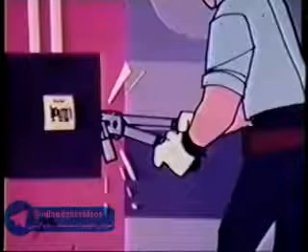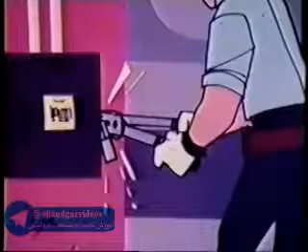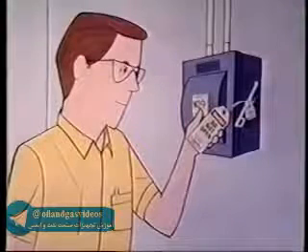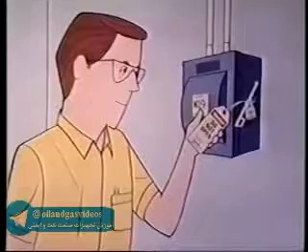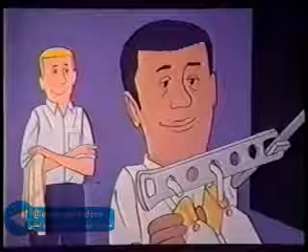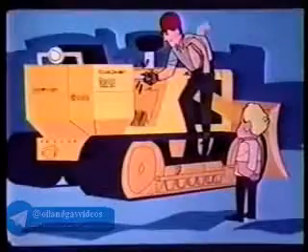The plant manager or designated person shall be responsible for cutting the lock. The missing person must have knowledge of the removed lock before resuming work. The supervisor should be responsible for properly executed departmental lockouts and the adequacy of the lockout procedure. When changing shifts, the relief person will attach his or her lock prior to the relieved person's lock being removed. The disconnect will always be protected during the procedure.